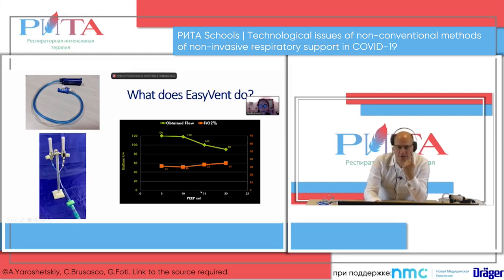Only use one inlet, A. Yes, this is the Venturi system's performance, and you have to test it using the inlet that creates the Venturi effect, which is the A one, the blue one for us. Then if you increase PEEP, you obviously get a decrease in airflow output, but the worst case is still 90, okay? 90 is perfect. And because of this high airflow, the FiO2 remains stable between 30 and 35.